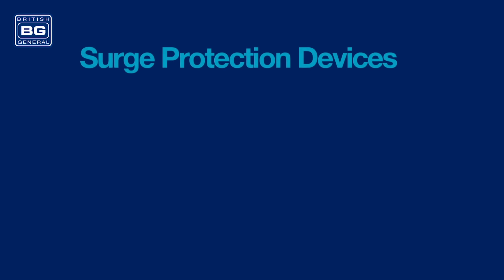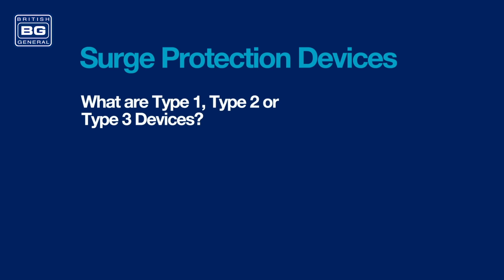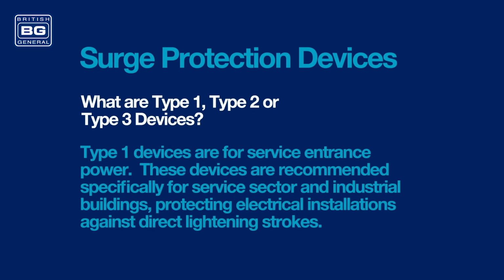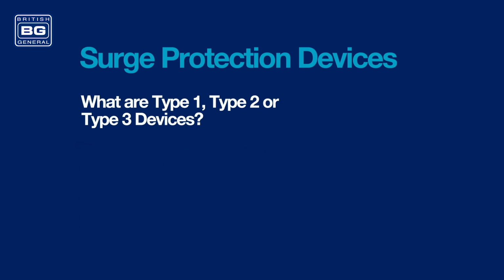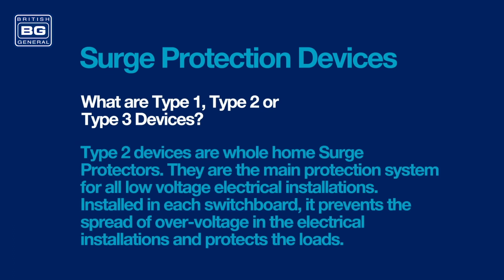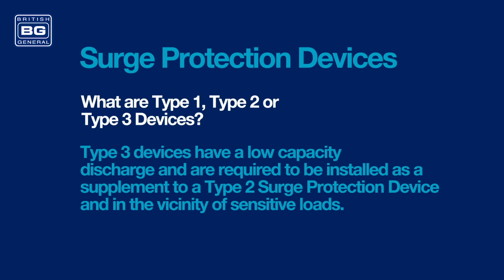Now, here are some frequently asked questions we've come across for surge protection devices in the 18th edition. What are Type 1, Type 2, or Type 3 surge protection devices? A Type 1 device is for service entrance power. These devices are recommended specifically for service sector and industrial buildings, protecting electrical installations against direct lightning strikes. Type 2 devices are whole home surge protectors. They are the main protection system for all low-voltage electrical installations. Installed in each switchboard, it prevents the spread of overvoltage in the electrical installations and protects the loads. Type 3 devices have a low-capacity discharge and are required to be installed as a supplement to a Type 2 surge protection device and in the vicinity of sensitive loads.